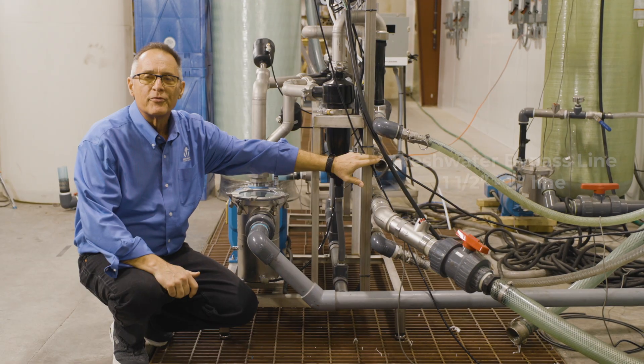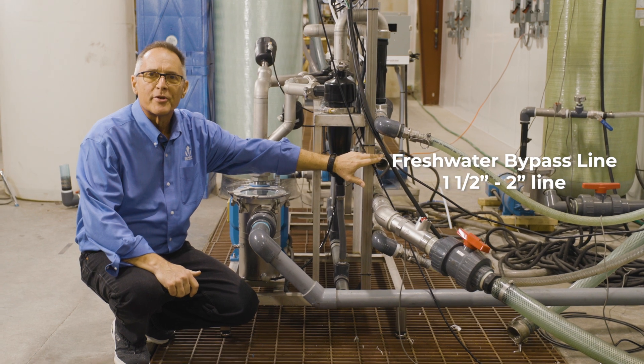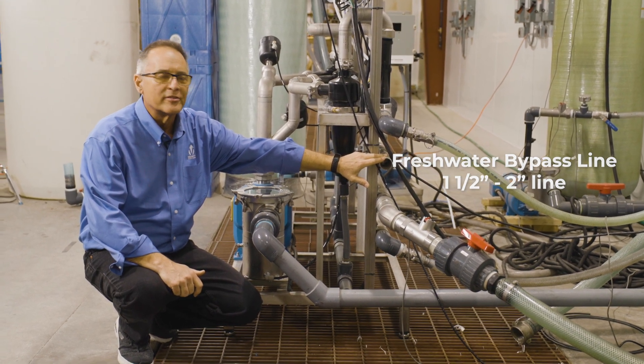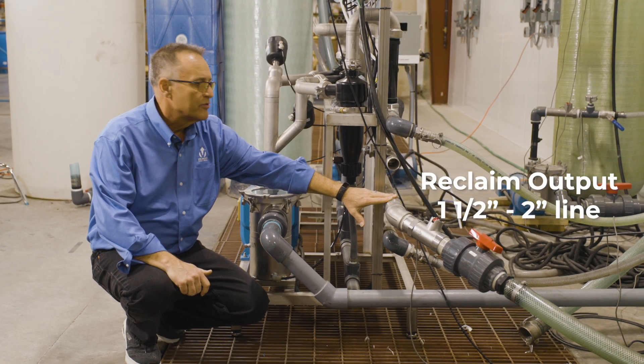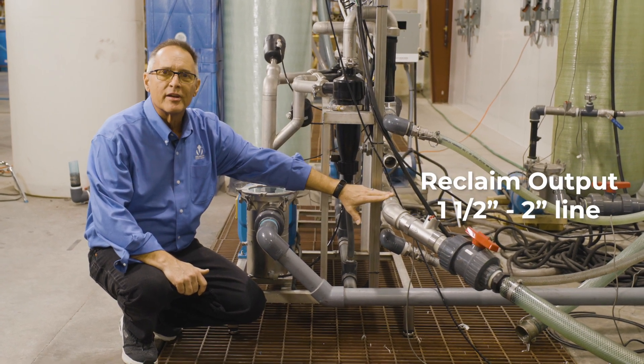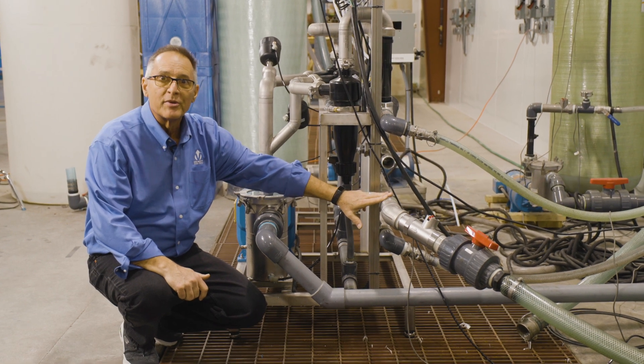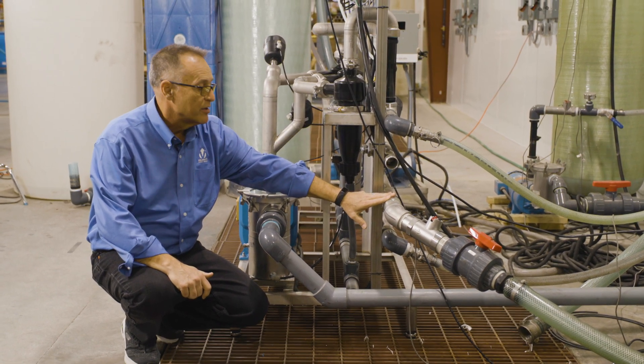Below that is your freshwater bypass line — your freshwater line coming into the unit — again inch-and-a-half or two inch depending on the size of the system. One below that is going to be your reclaim output, again inch-and-a-half or two inch depending on the size of the unit. This one in particular is an inch-and-a-half, 70 gallon-a-minute system, so we've sized the piping appropriately to the amount of water flowing out of the unit.